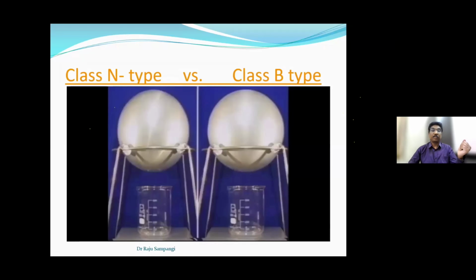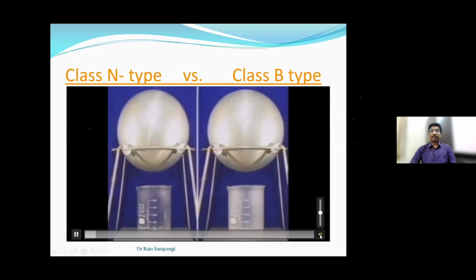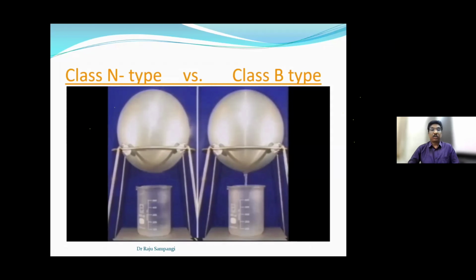That's the difference. Now, if you look at this video here, what we see is an example of the negative impact of remaining air during steam sterilization. So you have a Class N and a Class B autoclave here. Gravity or flash sterilization on the left side: an aluminum ball of a specific mass, equivalent to 10 kilograms of stainless steel, in a gravity chamber where no air was removed. On the right side, in a prevac chamber where air was removed. And the difference is clear.